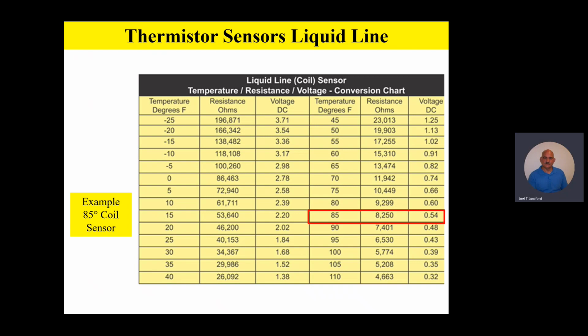And one final example with the liquid line sensor. Let's say we have a liquid line temperature or a coil temperature sensor, temperature of 85 degrees Fahrenheit. At 85 degrees Fahrenheit, if I unplug the sensor from the board, it should be about 8,250 ohms with the sensor unplugged off the board at 85 degrees. And if I plug it back onto the board and read that DC voltage at the back of that harness, it should be about 0.54 volt DC.